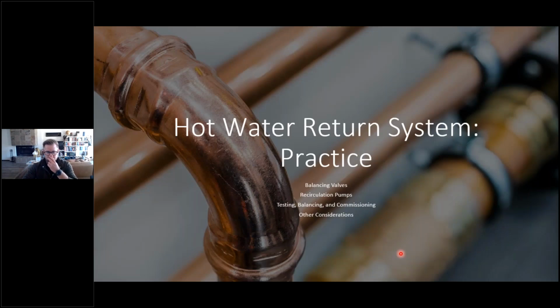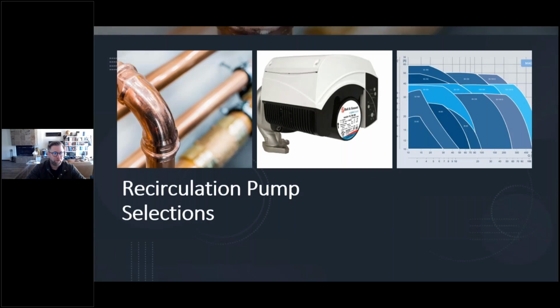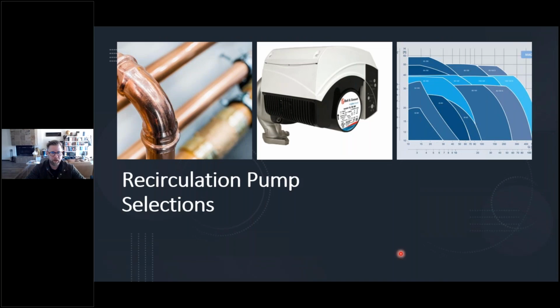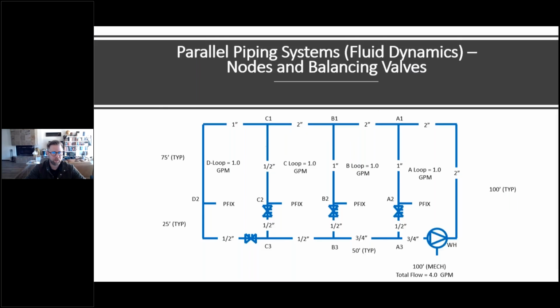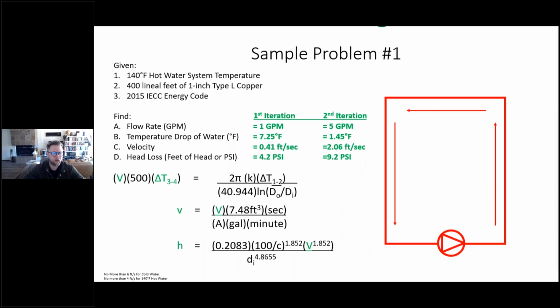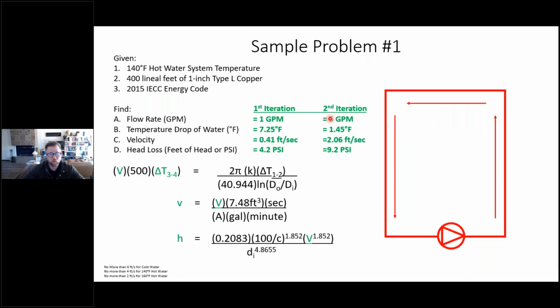Now, we'll have some time for questions here at the end, but that's kind of the end of the theoretical side. So let's talk practical, or practice. Theory and practice is what makes up expertise. So first off, when you're selecting your recirculation pump, right? When we went back through, let me go back a few slides here, and we got this result, the second iteration. Let's say we like the second iteration more. When we select the pump, we are not selecting the pump for 5 GPM and 2.5 feet per second of velocity. We're selecting the pump based off of 5 GPM and a 9.2 psi pressure drop, because the pump will need to overcome that in order to recirculate through the system.